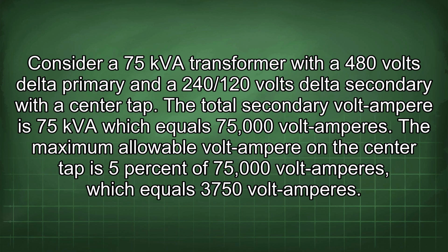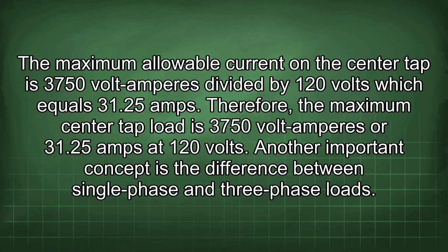The total secondary volt ampere is 75 kVA, which equals 75,000 volt amperes. The maximum allowable volt ampere on the center tap is 5% of 75,000 volt amperes, which equals 3,750 volt amperes. The maximum allowable current on the center tap is 3,750 volt amperes divided by 120 volts, which equals 31.25 amps. Therefore, the maximum center tap load is 3,750 volt amperes or 31.25 amps at 120 volts.